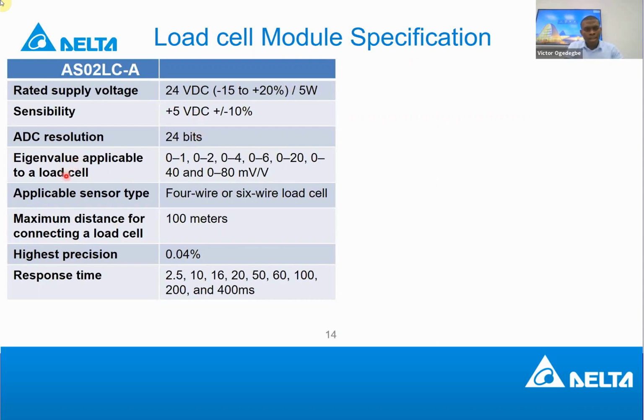And then this is what I told you is very important, the gain value. For each load cell or load sensor, the manufacturer has specified the gain value. It means that at the specified gain value, this would be the readout of the strain gauge of the internal sensor. And then we also have different types of sensor, 4-wire or 6-wire load cell or load sensor. And also the maximum distance that you can install the sensor far away from the module is 100 meters. See, it's quite big. It's like the length of a building. And then the precision is also very important. The precision of this load cell module is 0.04.